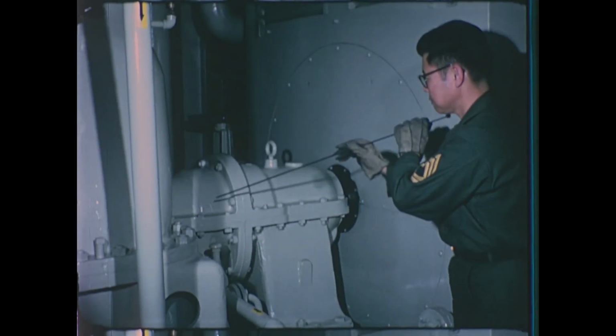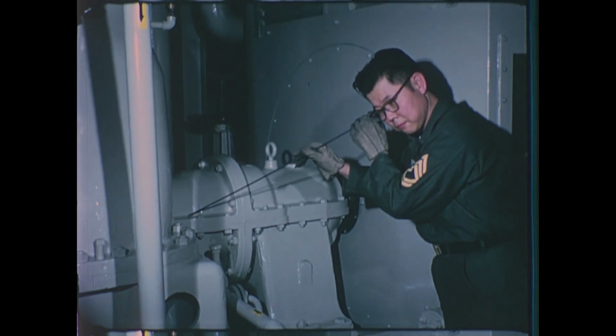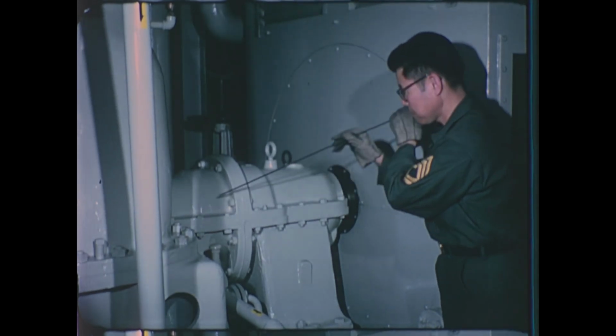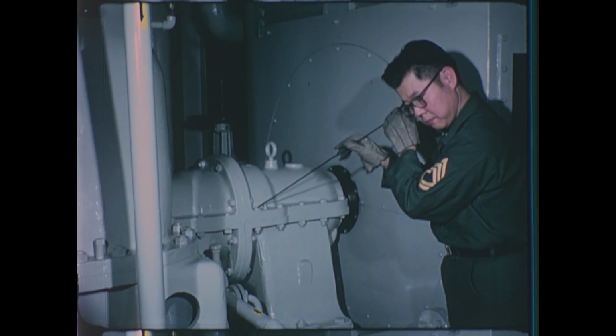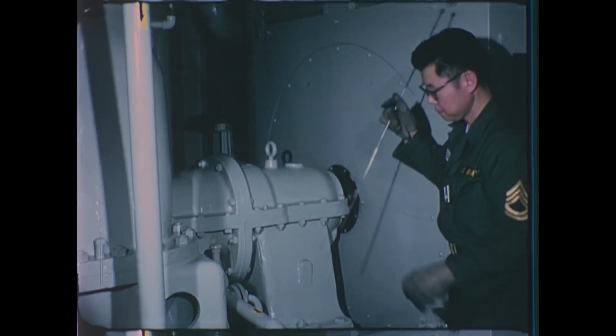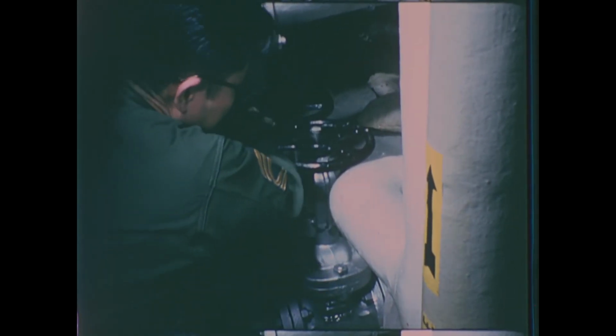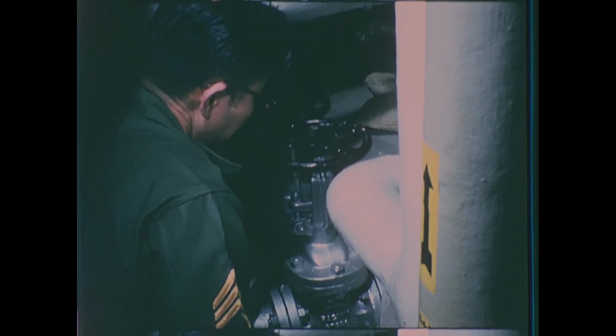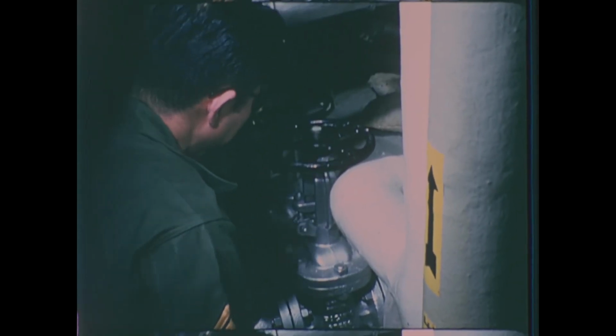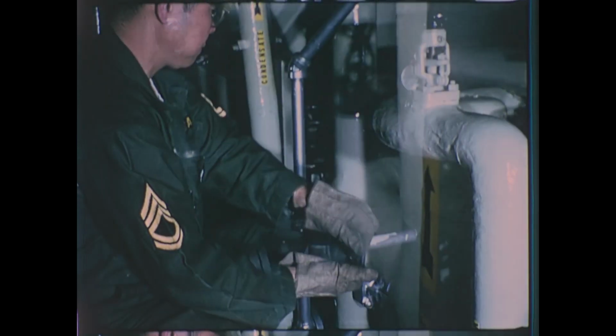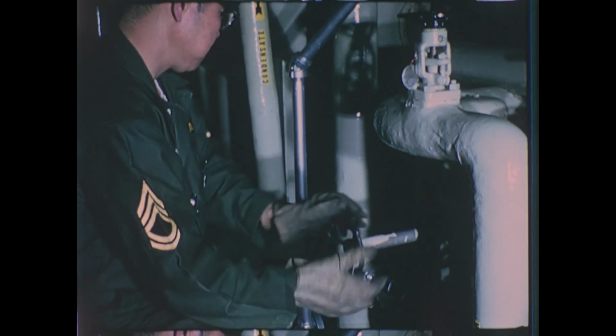When the turbine has been rolled and the speed reduced to about 300 RPM, a listening check is made to detect any rubs, vibration, or other unusual noises. Here, the operator is valving the air ejector to discharge from overboard to the air ejector after condenser. He adjusts the steam flow to the gland seal air ejector.